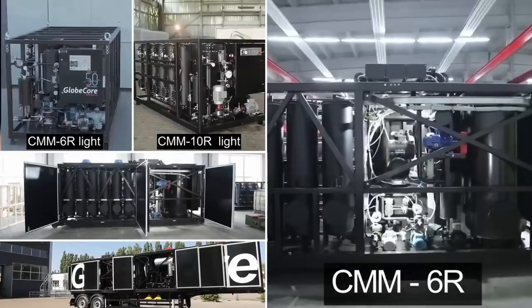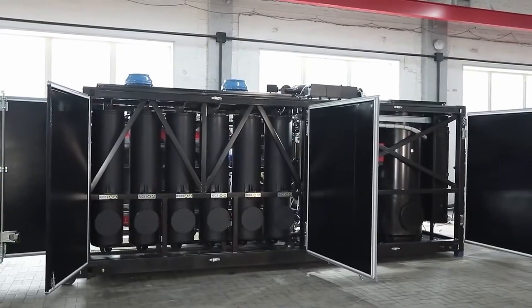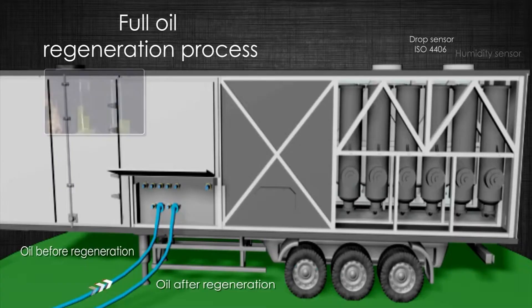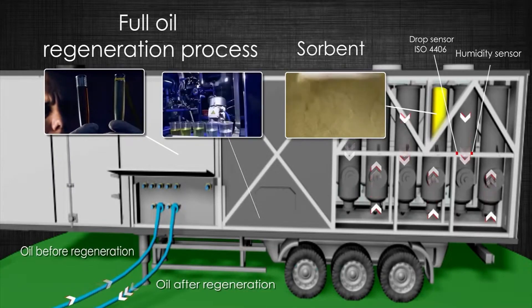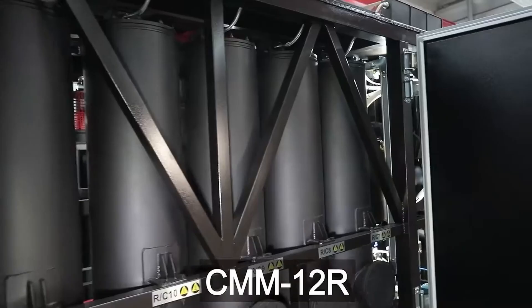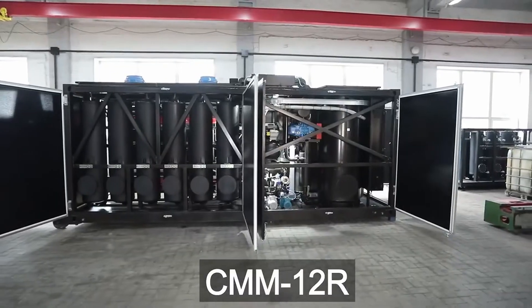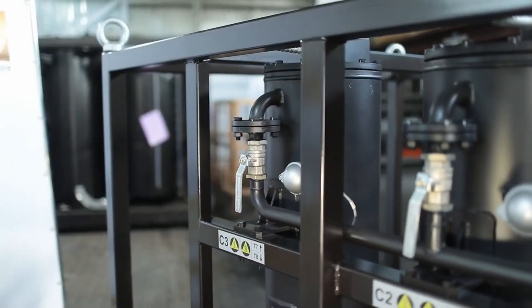These systems ensure polishing and clarification of dark-colored fuel oil and remove sulfur and hydrogen sulfide compounds. This is done with the use of columns filled with adsorbent. The number of columns depends on the customer preferences and determines the capacities of a fuel oil polishing system. The greater the number of columns, the higher the capacity.